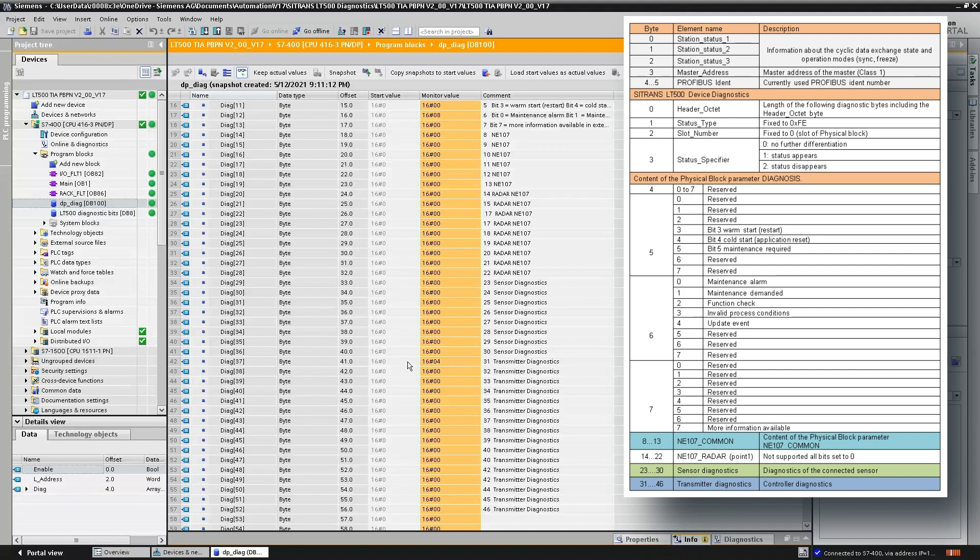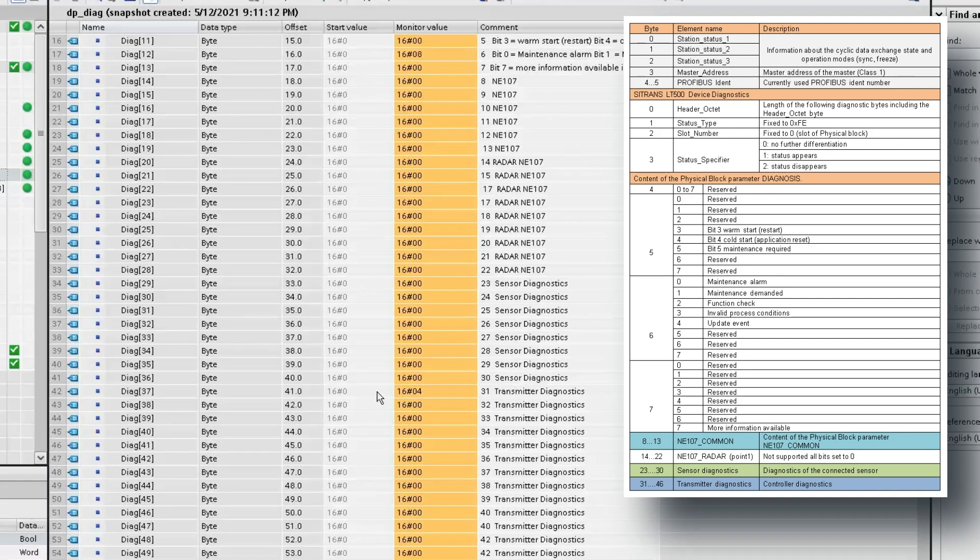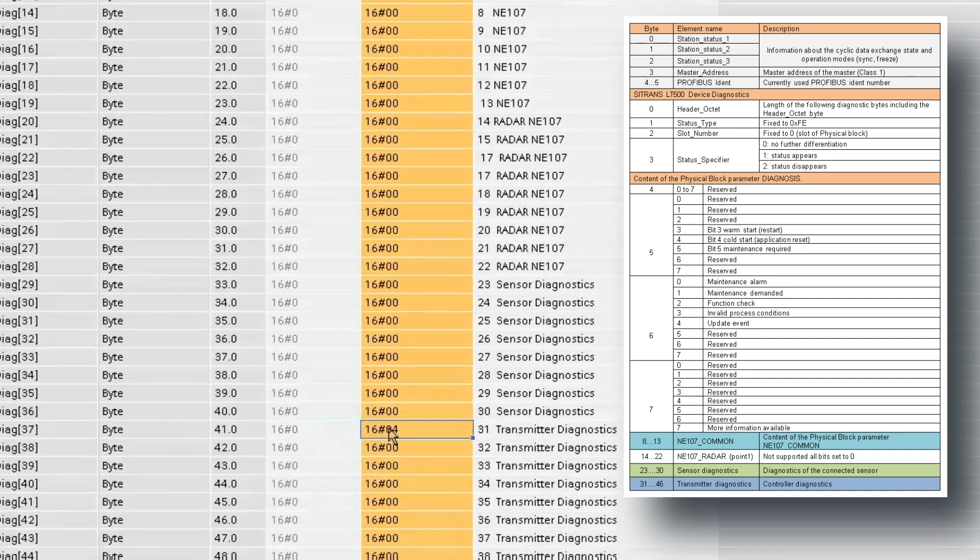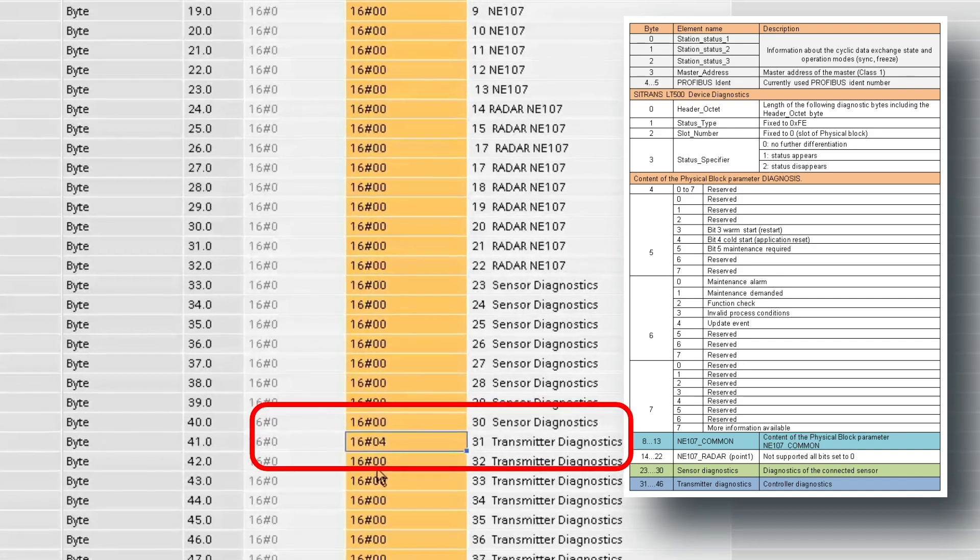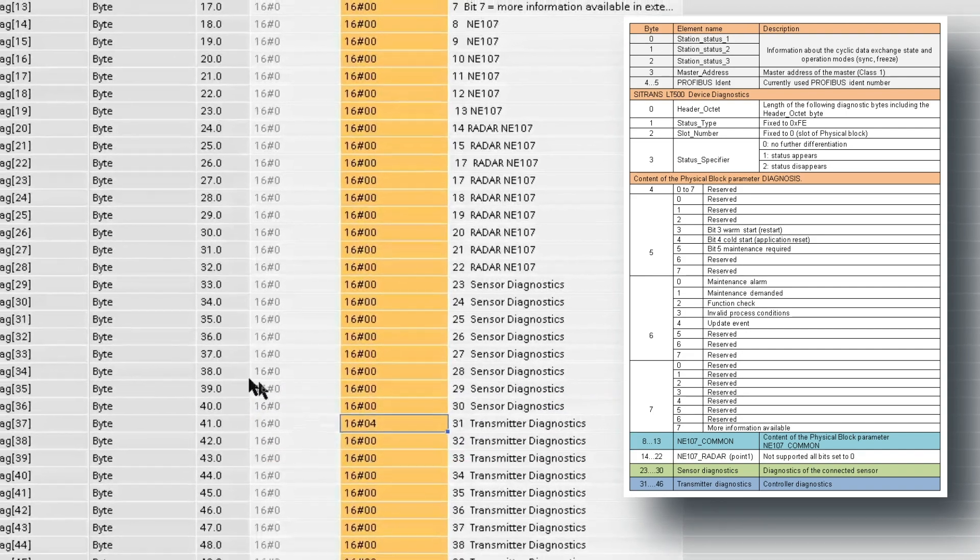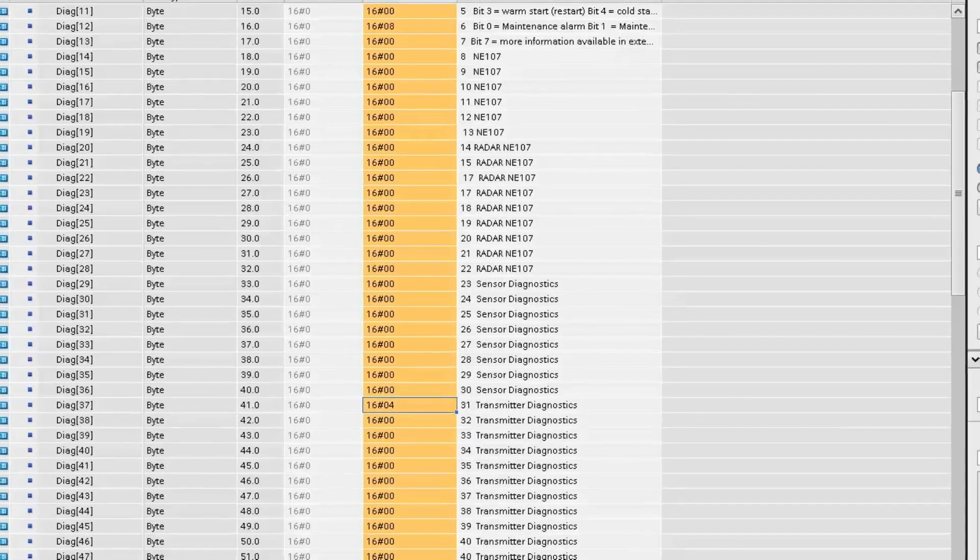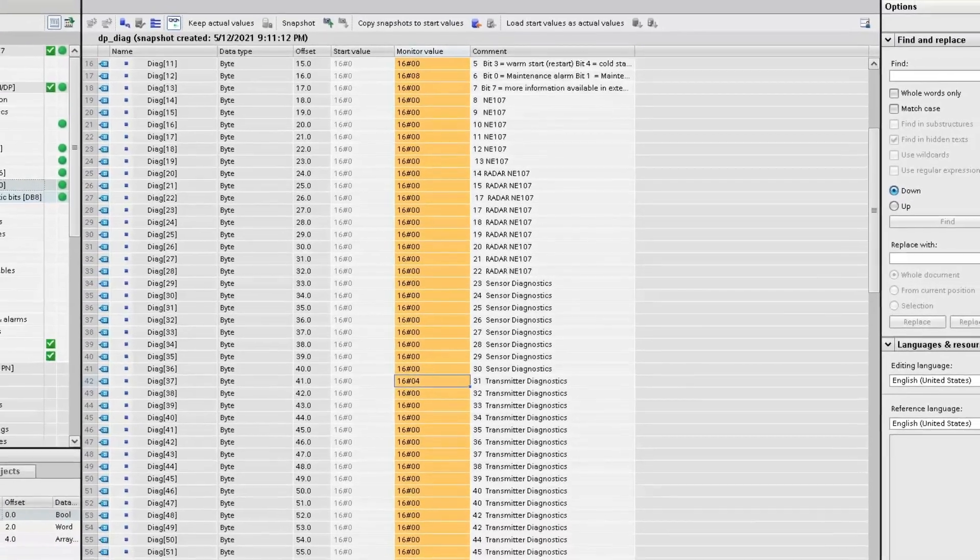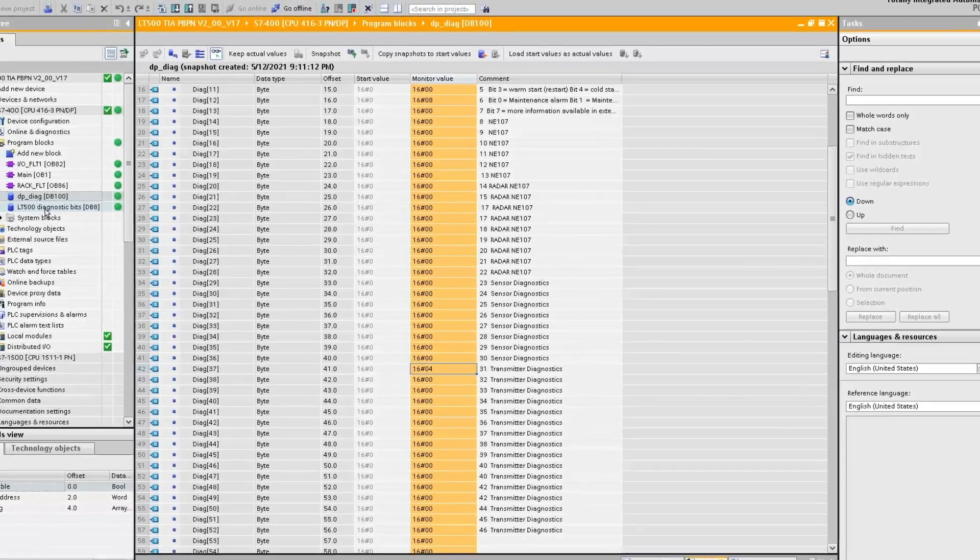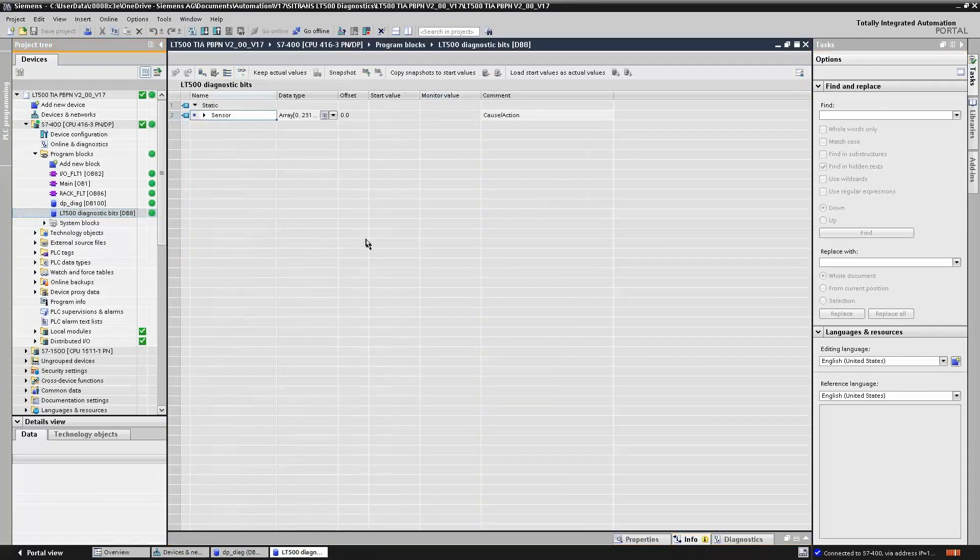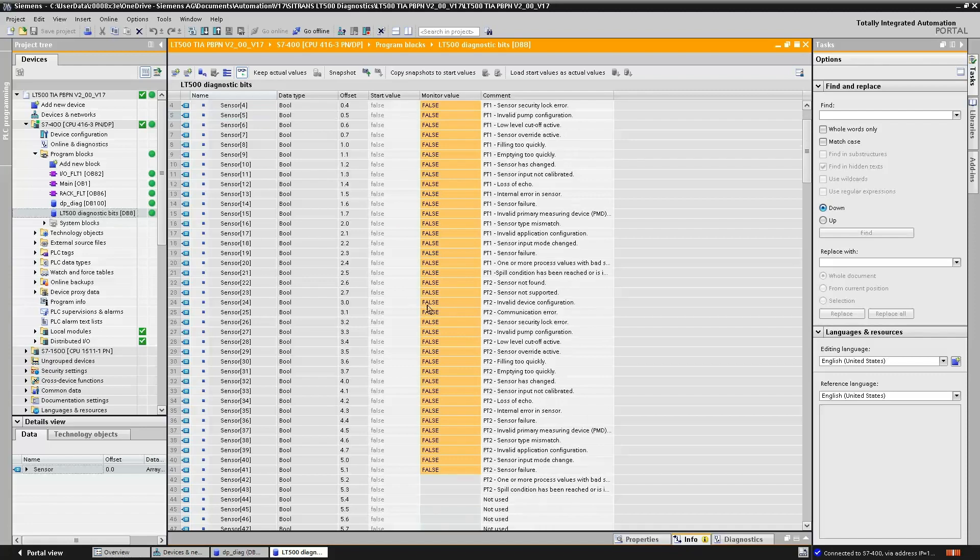If we drill in, we'll see that we have a byte here which has changed its status. If we delve in a little bit further and look at our diagnostics and refer to the manual, we can split out the bits and look in greater detail. What we've done in our program is just copy the sensor and transmitter diagnostics into another data block to make it easy to see what's going on.